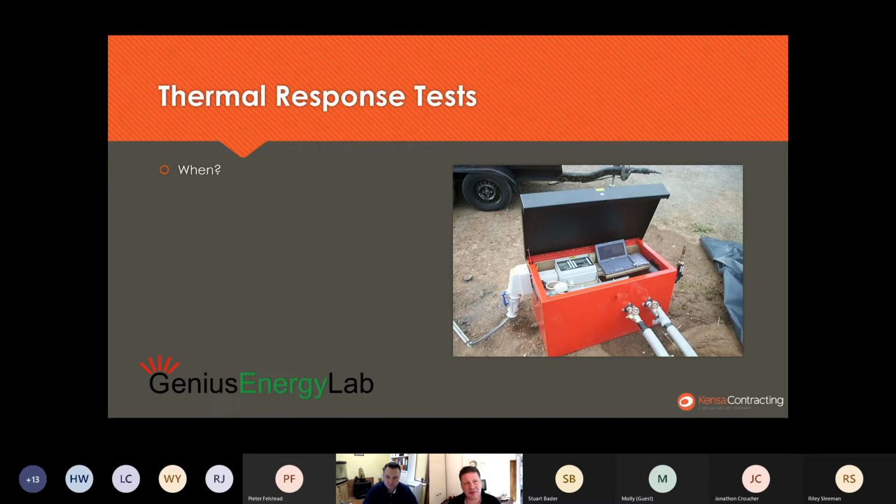I did touch base at the end of last time on marking a rule of thumb for that. If it's 0 to 10 boreholes, then it's probably not going to be justifiable to do the cost of this test. Tests range 2.5 to 3,500 to do the physical test on site and process the results. So to offset that in a 1 to 10 borehole system is probably unlikely.